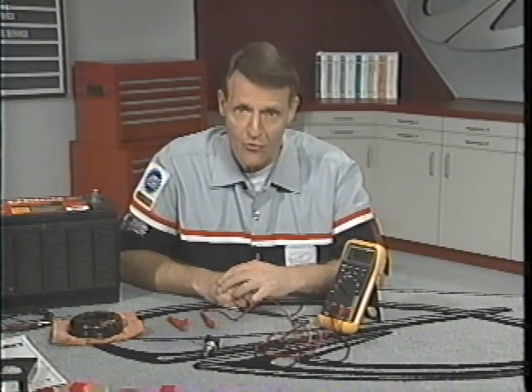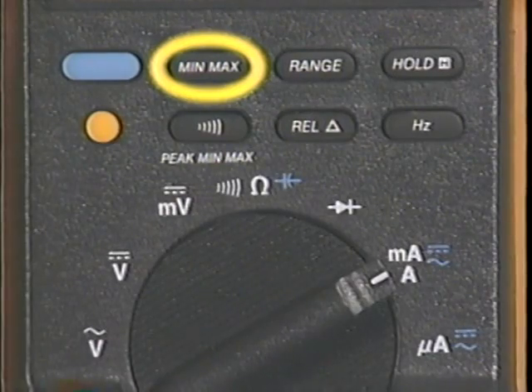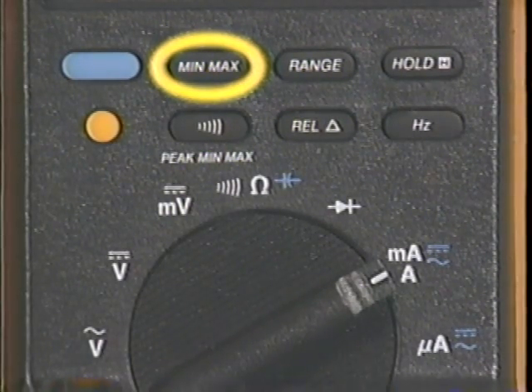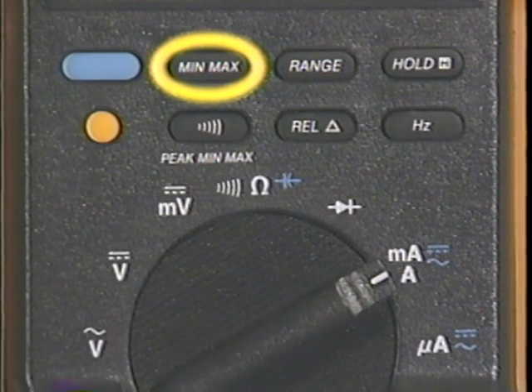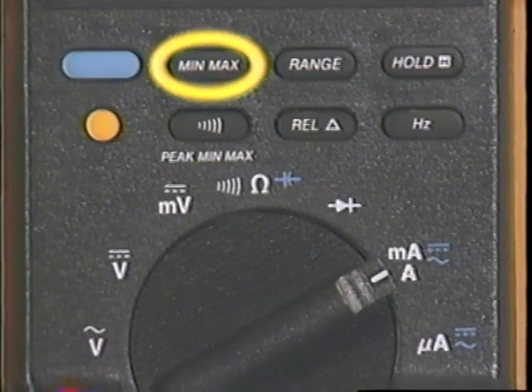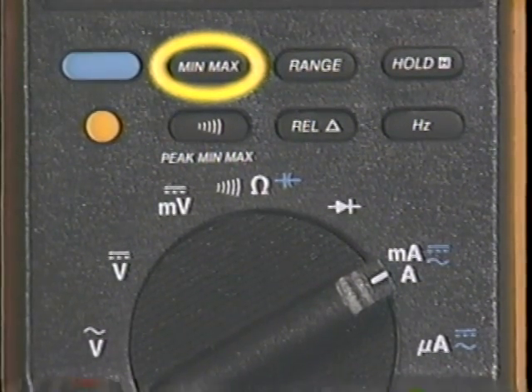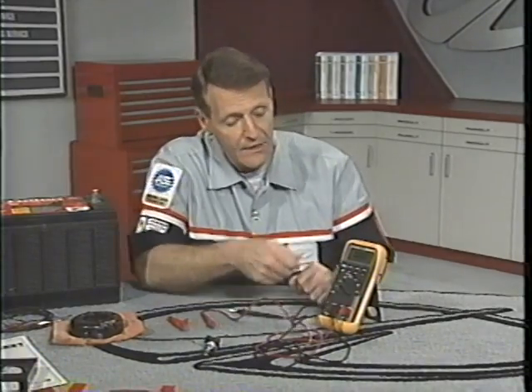Now for another function of the Fluke. We've said that you use the ammeter mainly to check for parasitic draw. And when you do that, you can get help from the meter's MinMax capability. In any of the major functions, MinMax captures the lowest and highest readings and computes the average reading over any period of time up to 36 hours. MinMax can capture readings as brief as 100 milliseconds, a tenth of a second, but to catch them, it doesn't have time to auto-range. So to use MinMax, you need to choose the function.